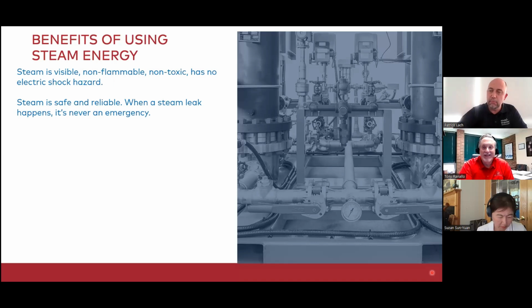How many times have I gone into a mechanical room, seen a steam leak, and gone back 5 years later, it's still there. When it's new, everybody's happy. When it's getting old, like old steam systems of 100+ years old, leaking everywhere, and nobody's fixing them, but no building is losing heat. This is how reliable it is, right? If it's a natural gas leak, everybody out of the building, or traffic jam downtown. Hot water leak, you better take care of it right now because you're going to have a hell of a mess. Steam, there's nothing to worry about with a steam leak.